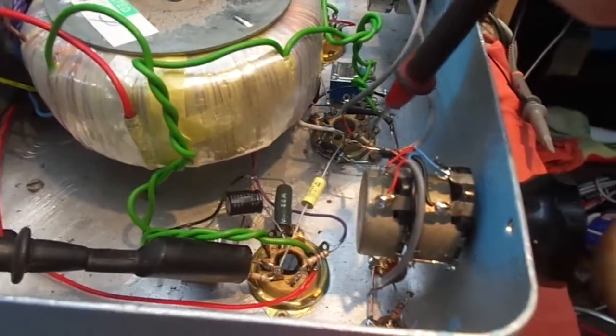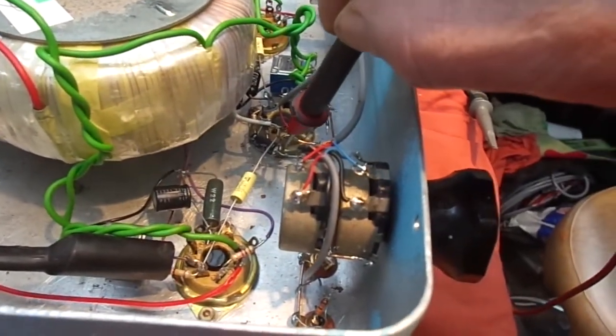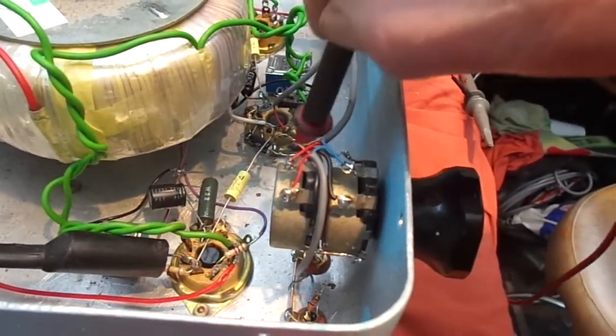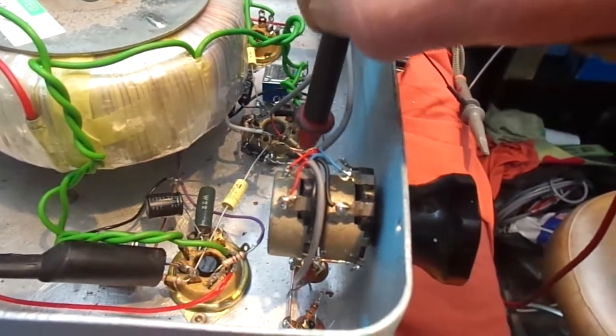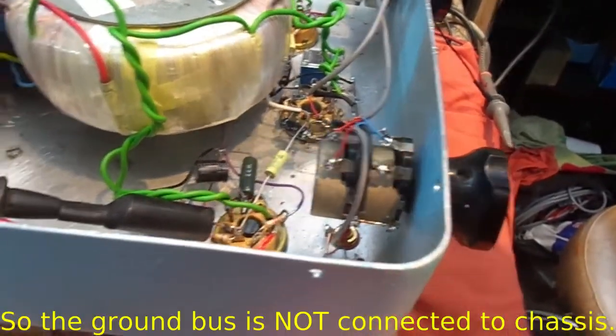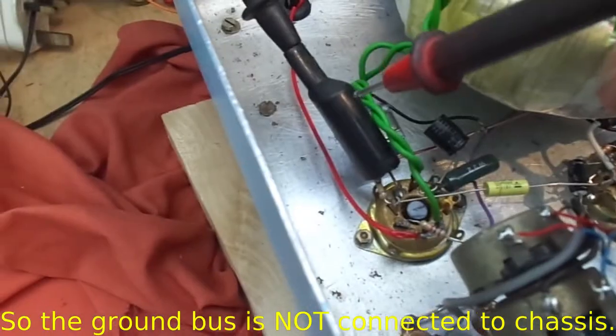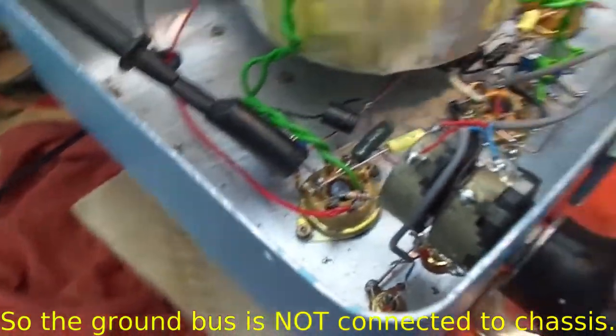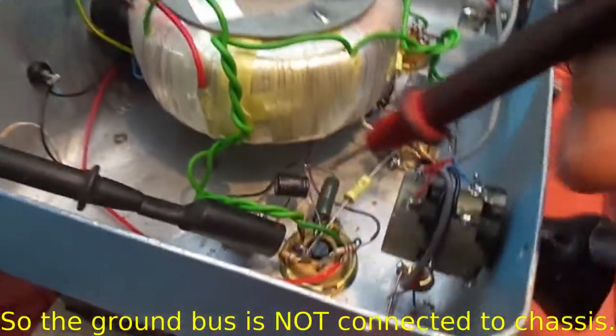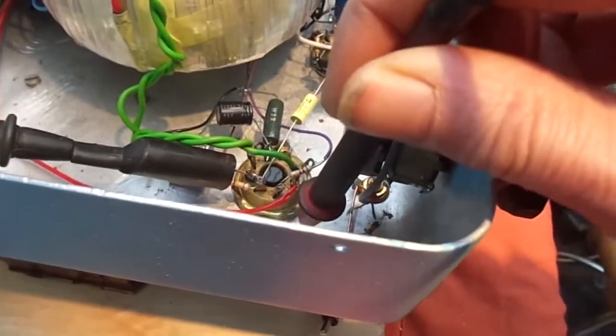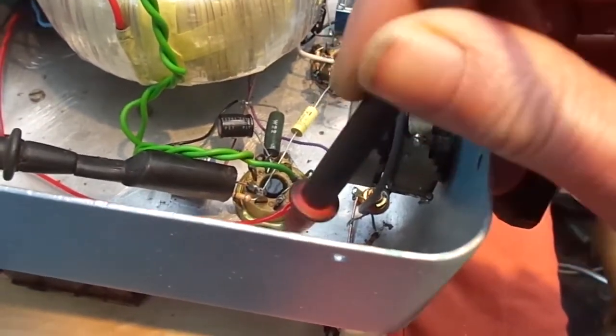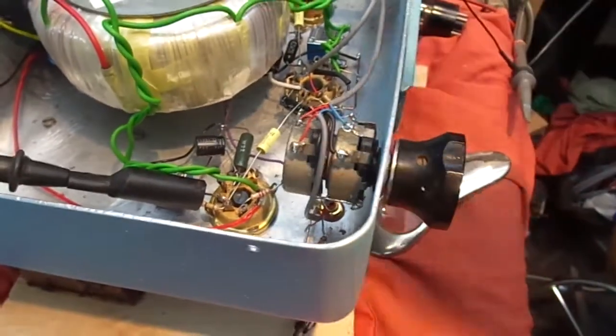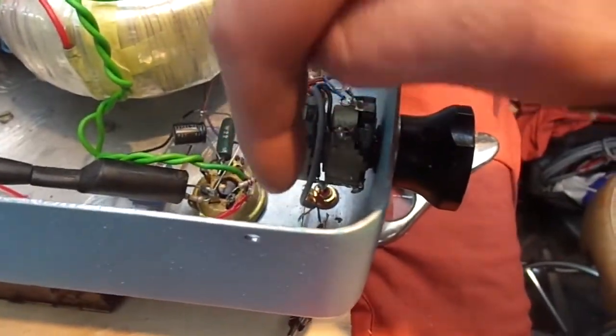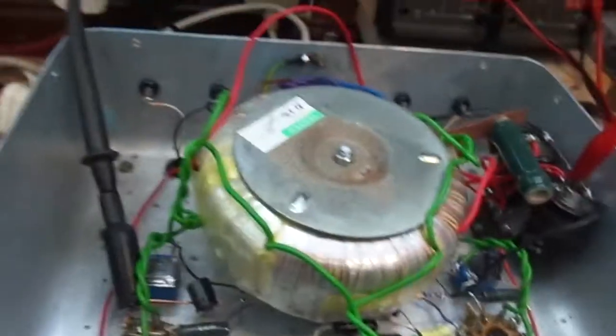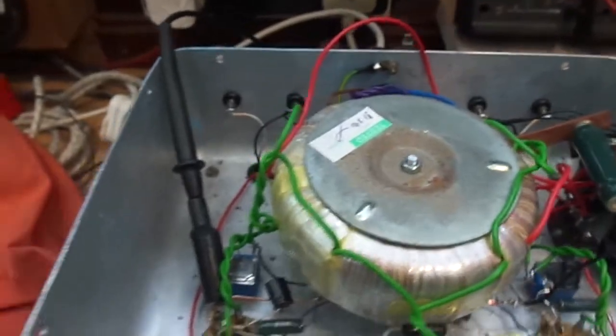Right, I've pulled that ground bus off that connection which goes to the valve socket which goes to chassis, and I've got one end of my probe on the ground bus, and this is the other end of the probe, meter on continuity. So somehow that ground bus is getting to the chassis, but it shouldn't be - it shouldn't be connected to the chassis.